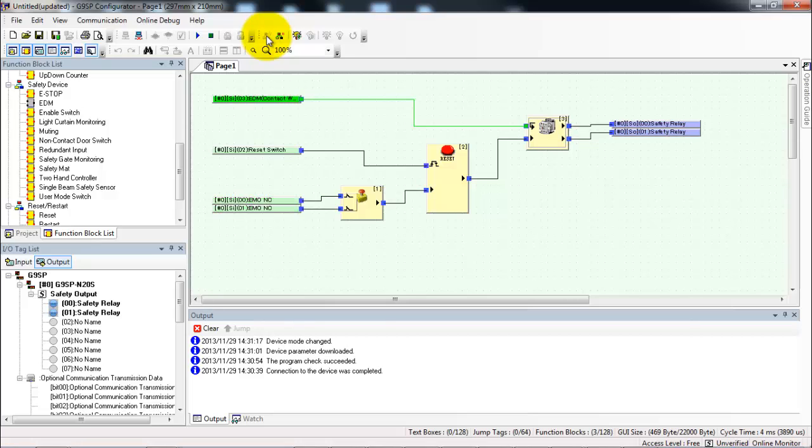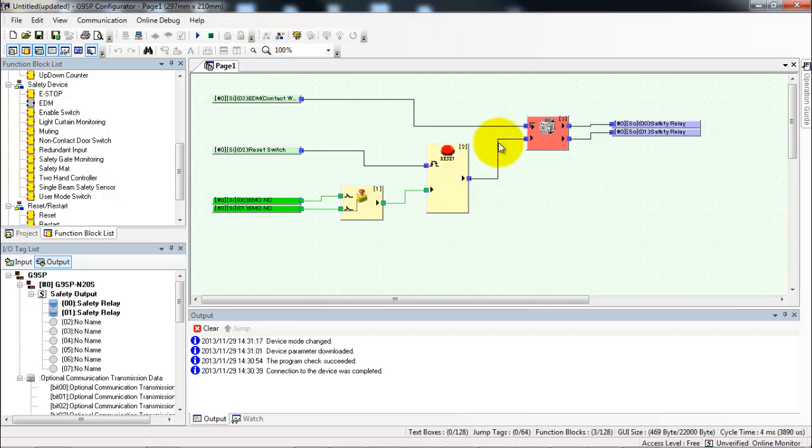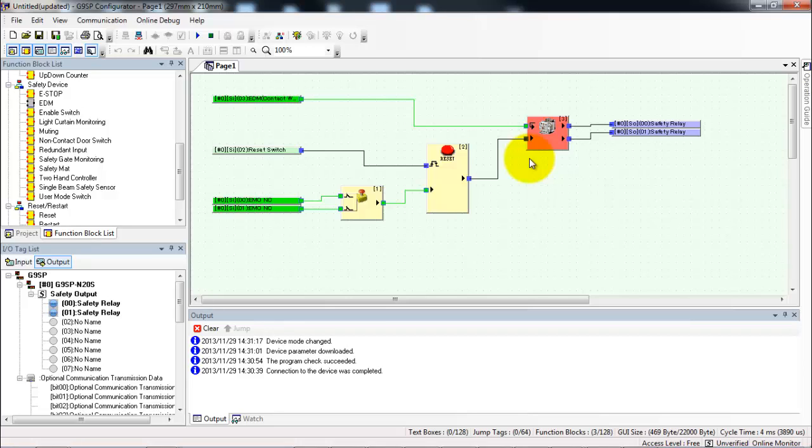Let me just show you the external device monitoring quickly. If I was to pop out this relay it detects that the EDM input is not in the right state and it makes the EDM function block go red showing that there's an error with the feedback signal. To correct that I'll put the relay back in and we will cycle the reset switch and now everything's back to normal again.